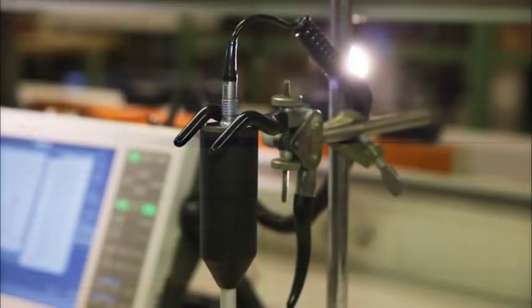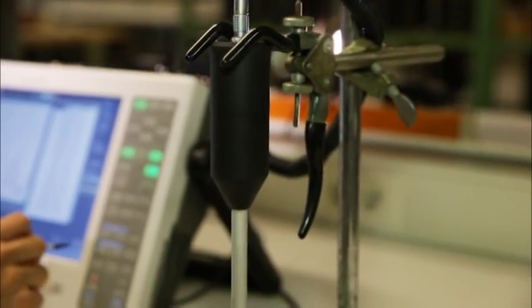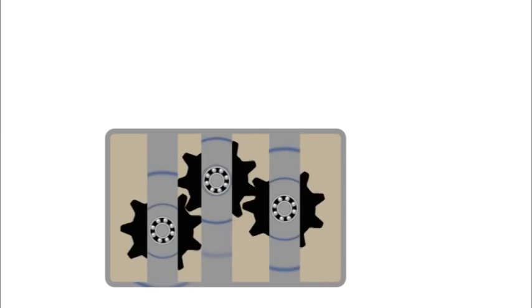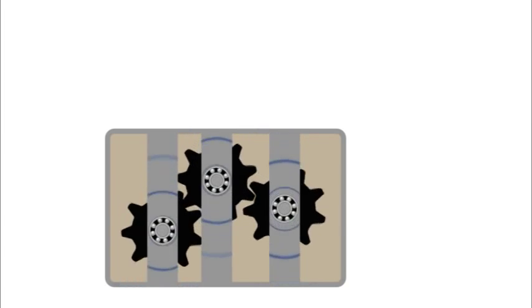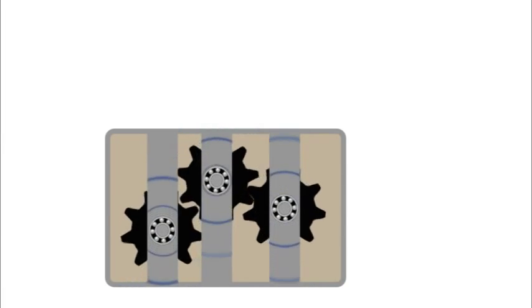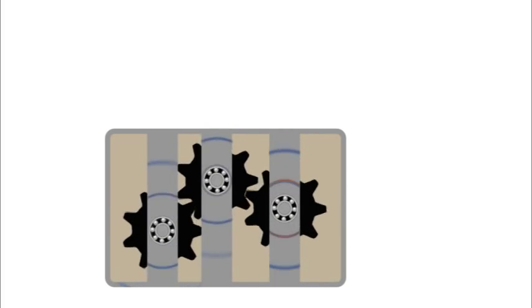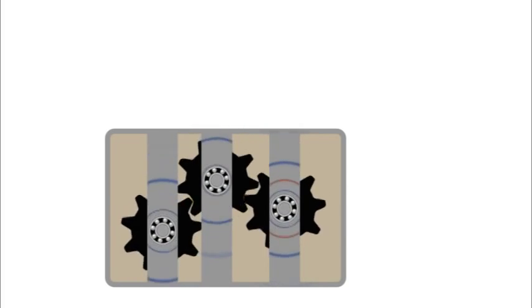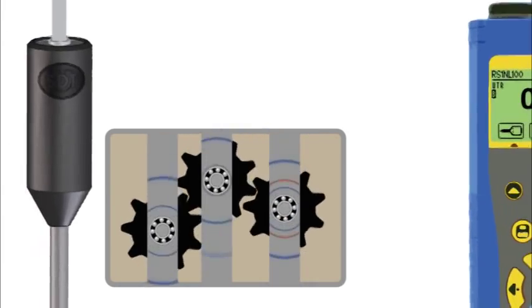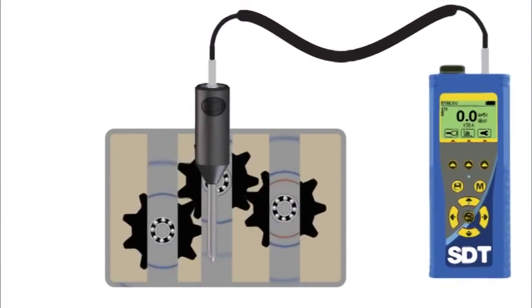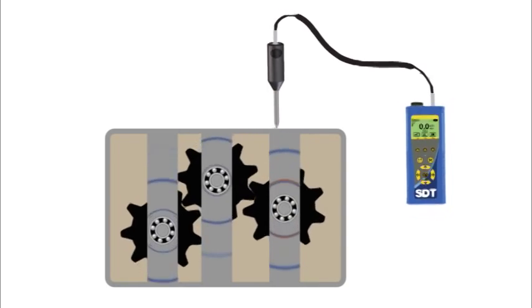Developments in sensor technology and data management software have established SDT at the front lines in the battle against unplanned bearing failures. All bearings, regardless of condition, produce ultrasound. Ultrasound is produced by normal or excessive friction forces. It can also be produced by impacting, rubbing, and misalignment or imbalance defects.